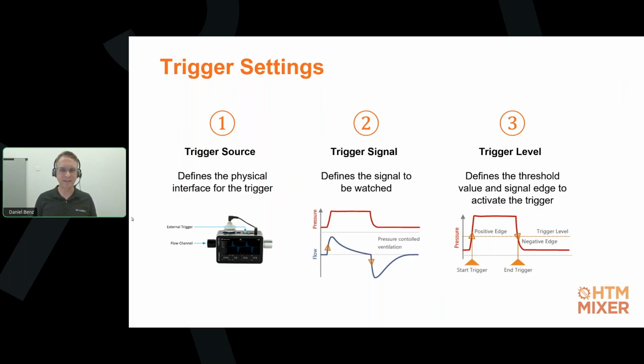Then the trigger signal defines which signal shall be used for triggering. Here you can typically choose between the pressure waveform or the flow waveform of your gas flow analyzer. For example, if you have an analyzer that measures pressure inside the flow channel and you want to use that signal as the trigger, you can set the trigger source to be the flow channel and the signal to be the pressure in the flow channel. And finally, the trigger level, number 3 here, defines the threshold value on this flow or pressure signal for the trigger to be activated.